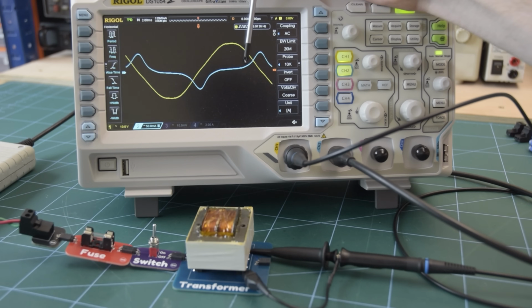At this point, our flux reaches the limit that the core can handle, and the core starts to saturate. But the voltage is still positive, so we're still trying to pump in more flux. The core can't handle any more, so the inductance drops, meaning we're dividing by a smaller number, so our current starts to rise dramatically.